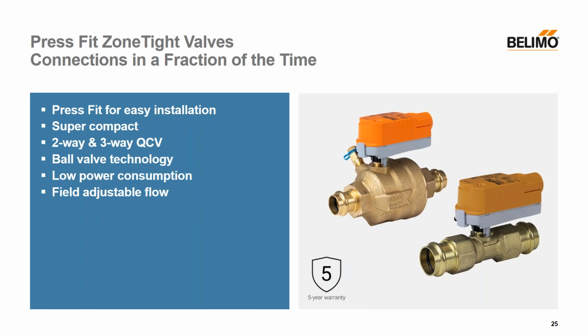Okay, new for 2022 is press fit zone tight valves. The PIQCVs are available in 1/2 inch to 3/4 inch, 0.9 to 9 GPM in non-fail safe and electronic fail safe. And these can be found under the energy valve pressure independent valves tab in section 8. QCV are available in 1/2 inch through 1 inch, 2-way and 3-way in non-fail safe and electronic fail safe, and are found under the zone valve tab in section 10. These feature the same zone tight compact design using ball valve technology for tight 0% leakage and are field adjustable for precise control.